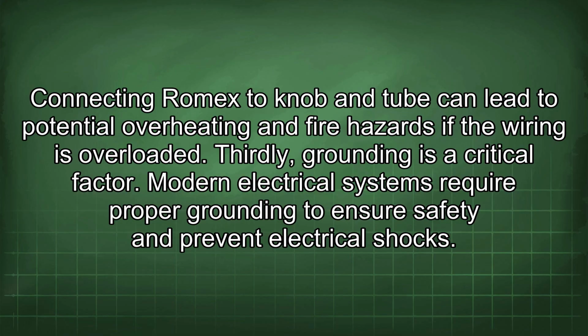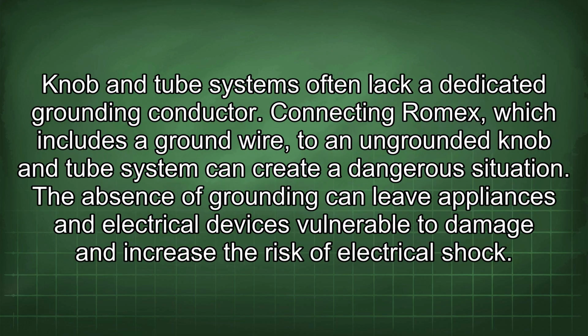Thirdly, grounding is a critical factor. Modern electrical systems require proper grounding to ensure safety and prevent electrical shocks. Knob and tube systems often lack a dedicated grounding conductor. Connecting Romex, which includes a ground wire, to an ungrounded knob and tube system can create a dangerous situation. The absence of grounding can leave appliances and electrical devices vulnerable to damage and increase the risk of electrical shock.